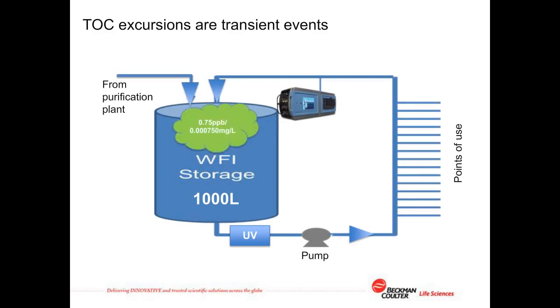The 750 micrograms per liter of carbon now enters the water for injection storage tank, which in our example contains 1,000 liters of water for injection. The 750 micrograms of carbon is now diluted in that 1,000 liters of water and becomes just 0.75 micrograms per liter, or 0.75 parts per billion. This diluted carbon is very easily destroyed by the UV lamp commonly used for microbial control on water for injection systems, as the water passes back out from the storage tank into the distribution loop.